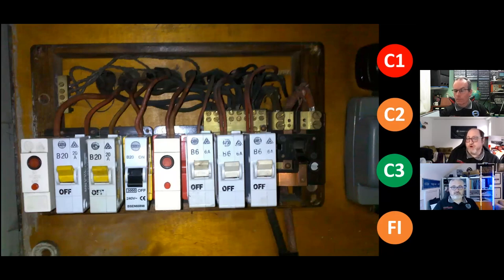Yeah. All right. So you're going to have to then at that point detail specifically what you have inspected, because it could be that there is a hidden danger in this system. Yep, a C1, a potential fatality, which you're now not going to see because you've chosen to stop. If you do that, you need to make sure you document clearly why you stopped and where you stopped. It comes down to extent and limitations.